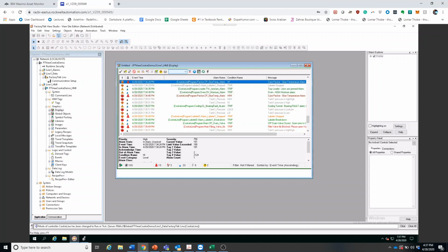In many cases, it is useful to have additional process information associated with an alarm. When an alarm is defined, you can associate up to 4 tags with the alarm at runtime. The tag values are recorded in the alarm and event history log, and can also be displayed in the alarm and event summary or alarm and event log viewer.